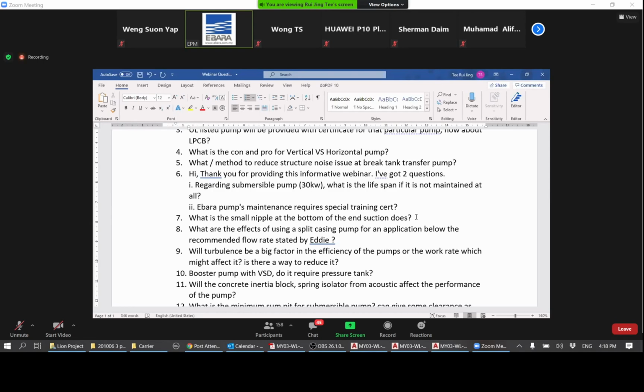Our pump is civil equipment, and you must have a maintenance plan, whether you want to take it out from your client's point of view. They must have a maintenance plan for these pumps before they hoist it. For your submersible pump, you need the hoist equipment to be at the designated position, and that they need to inspect it every year to show that the right equipment is being used. Your pit also has to be cleaned, very important, otherwise if it fills up with all kinds of rubbish and so on, it will affect the operation when they hoist the pump.